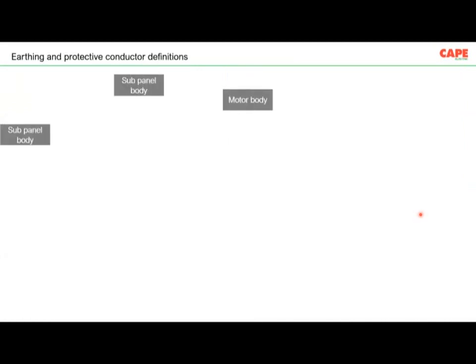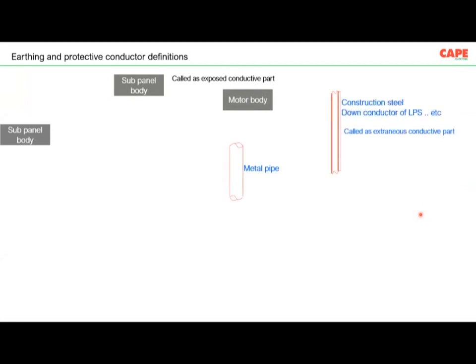Now, how to do earthing in a building? What kind of connections are required? What are the terms used? In your building, you will have exposed conductive parts such as the panel board body and motor body. Exposed conductive parts are applicable for class 1 equipment, not for class 2 equipment. Then your installation will also have extraneous conductive parts, such as construction steel, metal pipe, metal handrail, sometimes aluminium facade, the frame of the aluminium facade, and all these are called extraneous conductive parts.